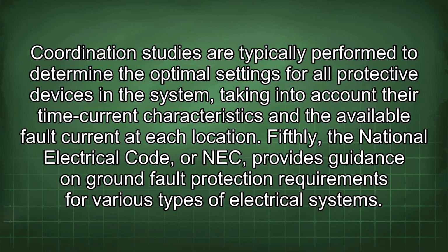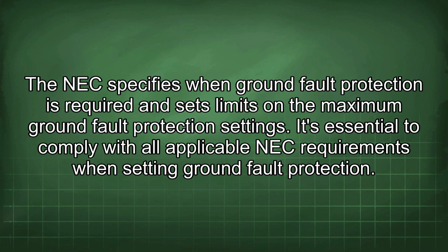Fifthly, the National Electrical Code, or NEC, provides guidance on ground fault protection requirements for various types of electrical systems. The NEC specifies when ground fault protection is required and sets limits on the maximum ground fault protection settings. It's essential to comply with all applicable NEC requirements when setting ground fault protection.